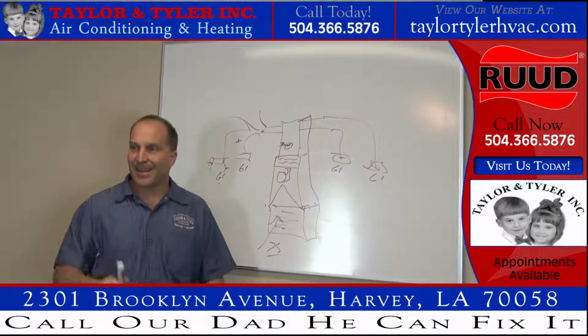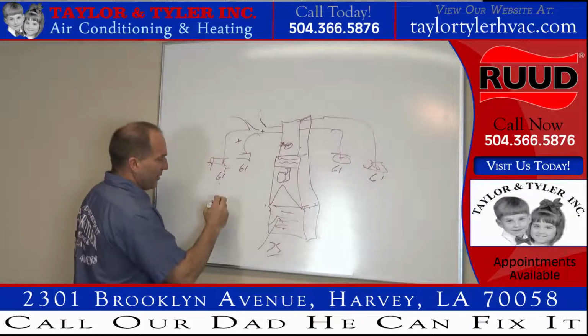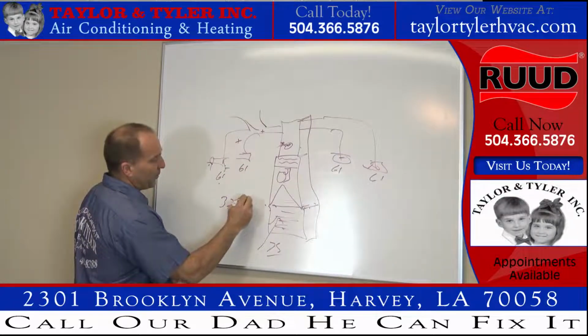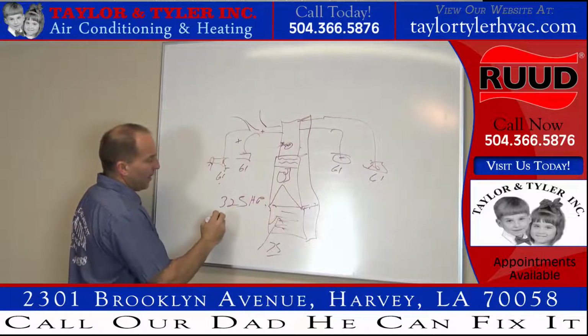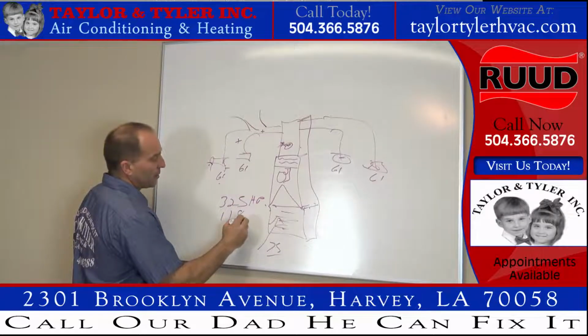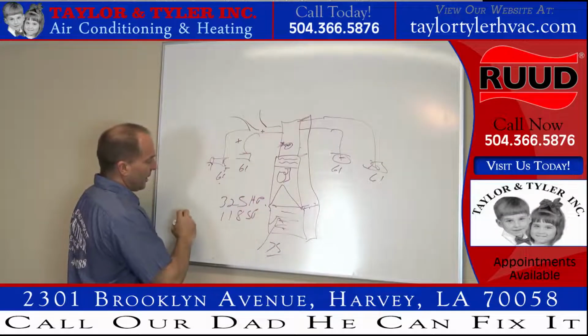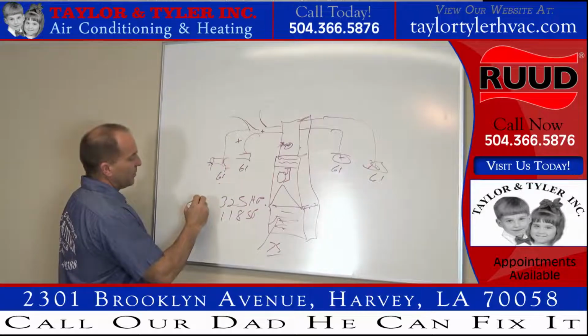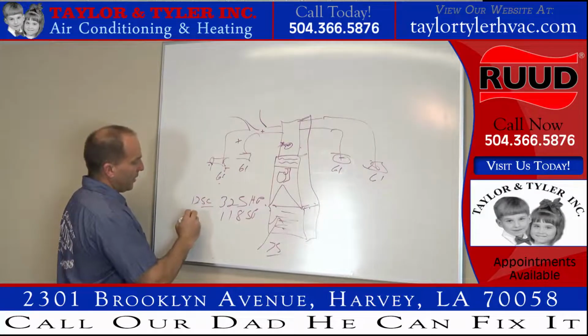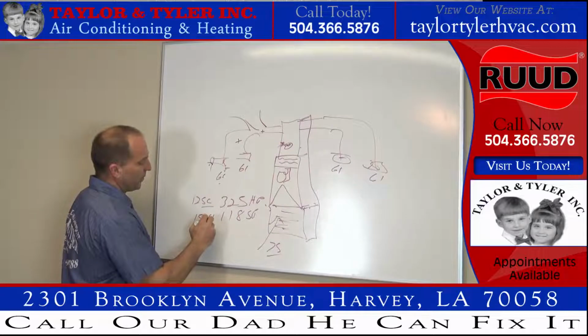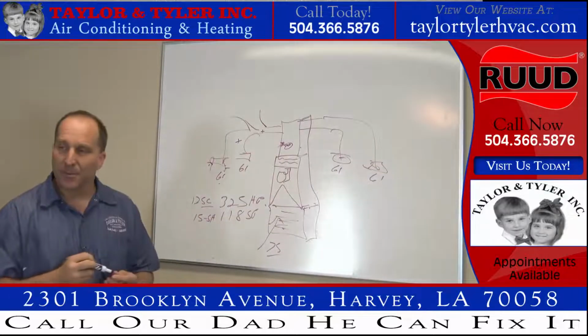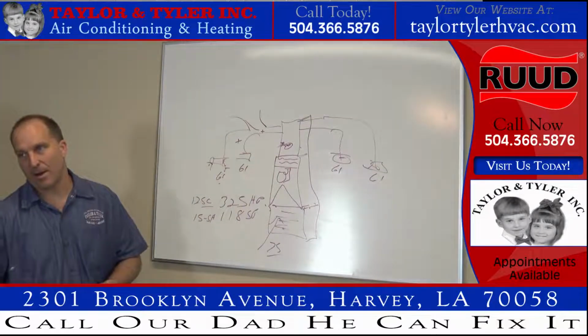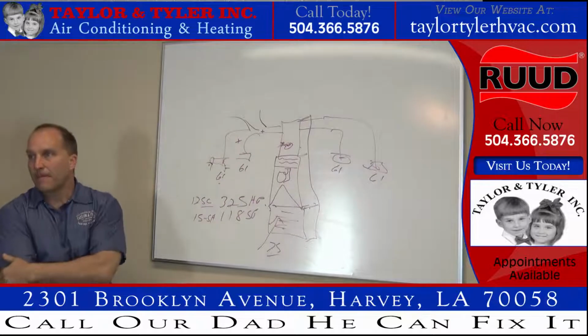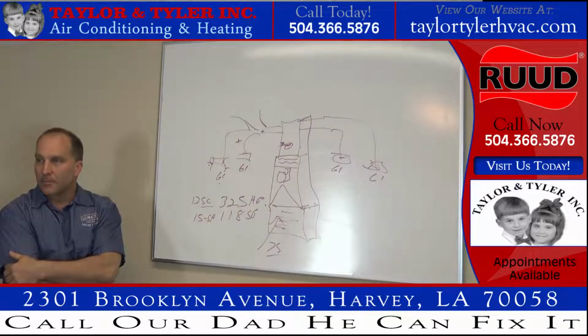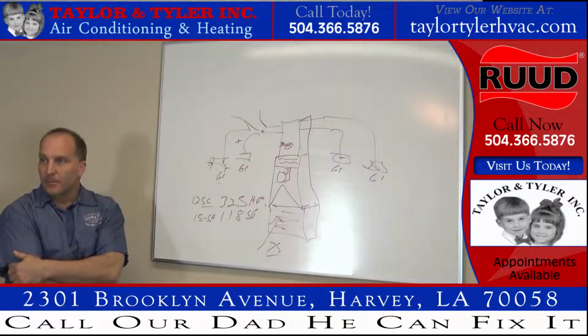In this case, I got a 325 pound head pressure, a 118 pound suction pressure, a 12 degree subcooling, and a 15 degree superheat, right? My pressures are absolutely perfect right now, guys. That's because everything's happening. It's those heater coils. One of them is stuck on.